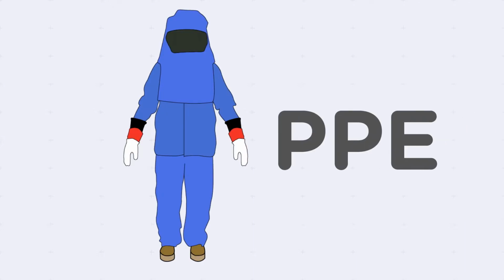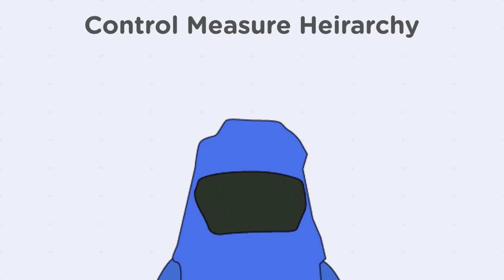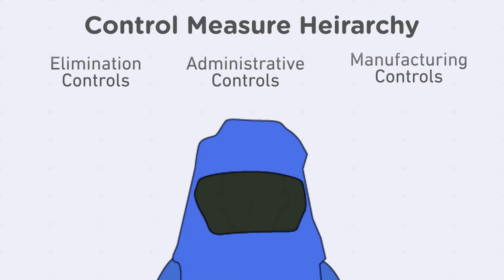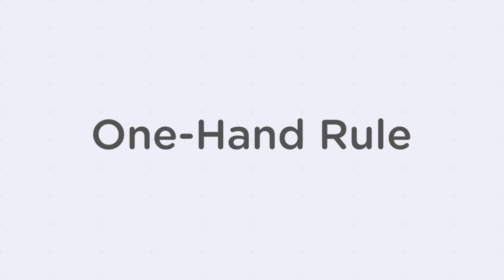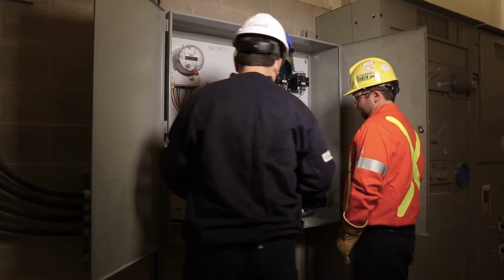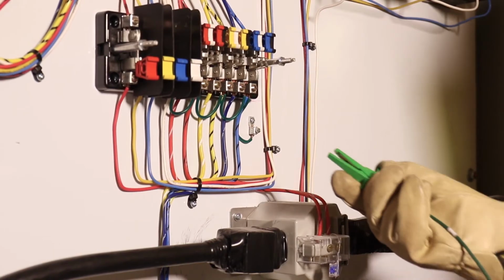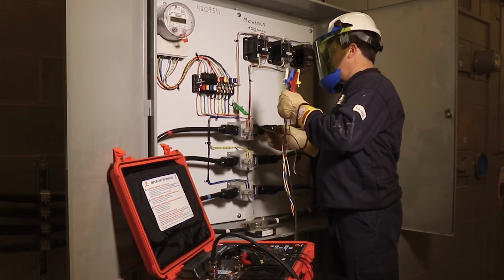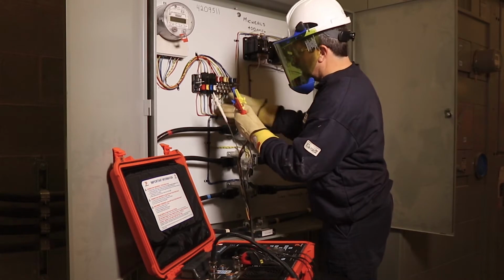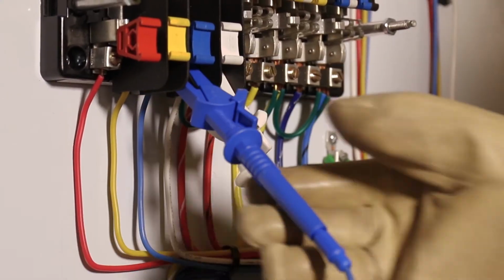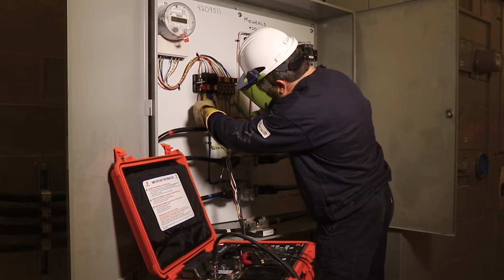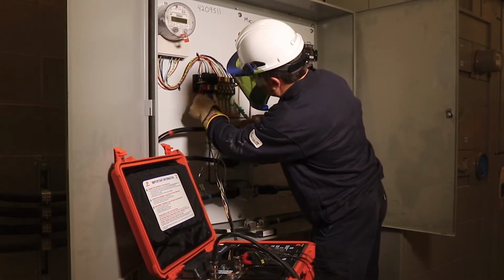PPE will always be required when the potential for arc flash exists. However, it's important to remember that PPE is at the bottom of the control measure hierarchy, and other control measures, like elimination, administrative, and manufacturing controls, should always be considered first. You can minimize risks by complementing PPE with safe work practices, like the one-hand rule. When connecting and disconnecting test equipment, use only one hand to take the body outside of the flash protection boundary. Stand to the side of the metering equipment, and make sure to inform others of your actions in advance.